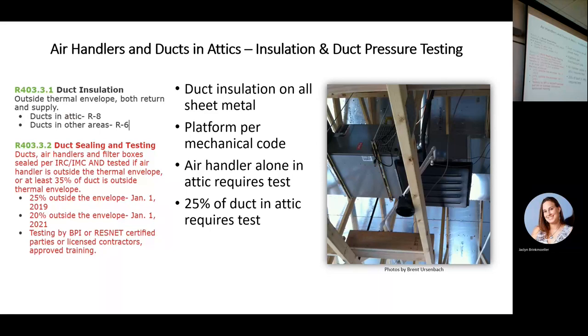If you just have the air handler outside the thermal envelope, you have to test the system. If you put your furnace in the garage, you should be testing the whole system because your air handler is not inside the thermal envelope. Now, the way you can get away with it is if you define your thermal envelope to go around the furnace room and put it in the house. Does that make sense? If you build a tight fitting room and insulate it, that's actually part of the envelope, you know, put a tight fitting door, insulate the walls. Yeah, if you create it so it's part of the envelope, but then it better be direct vent. Right? Right. Because of our previous discussion.